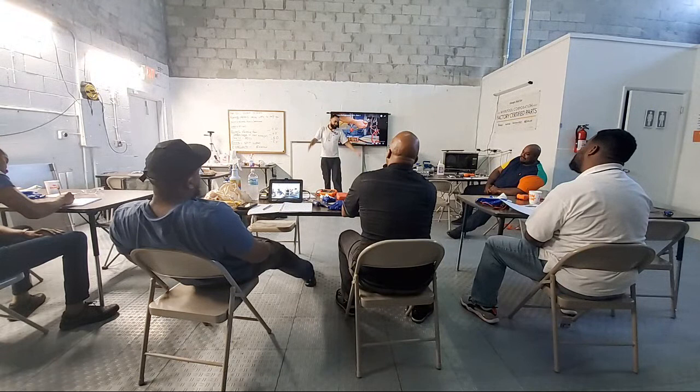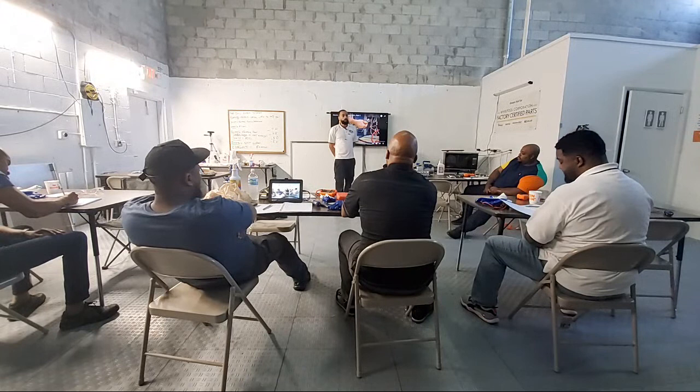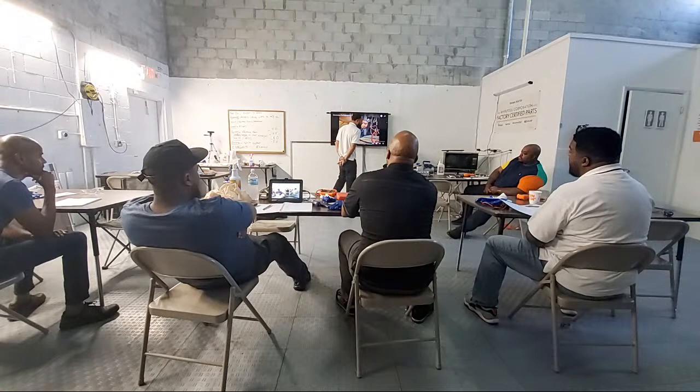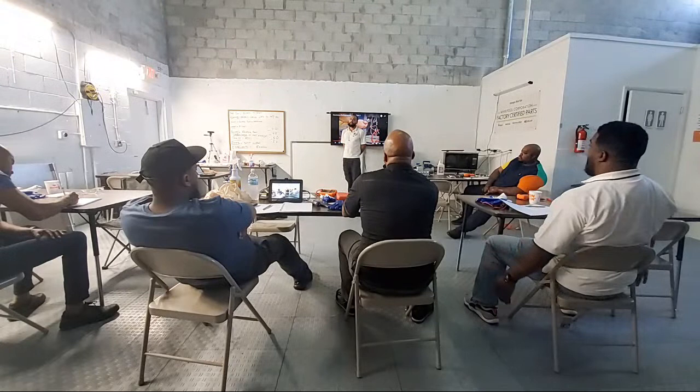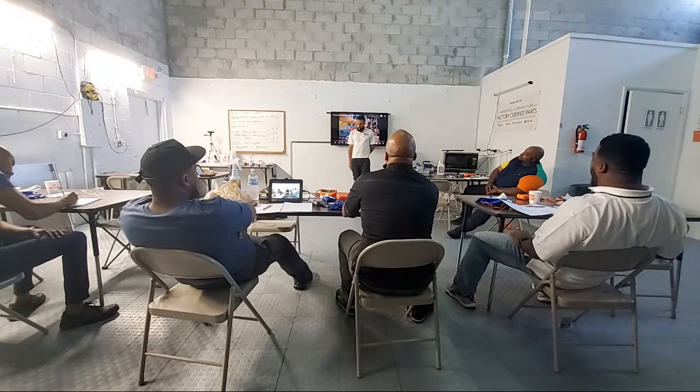All right. So sealed system. We're gonna tap in. Operating pressures normal are what? We spoke about this. Zero on both sides and 120. Let's say we get there and we see the compressor is burning hot, it's running, or super cold, whatever, it's just running. We actually can feel it. We can feel it running.